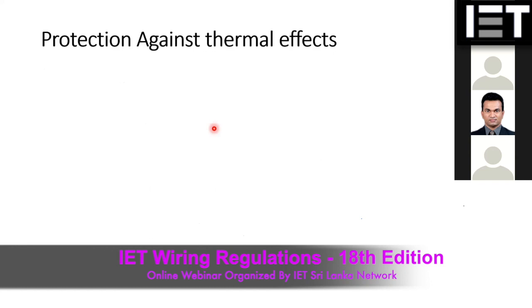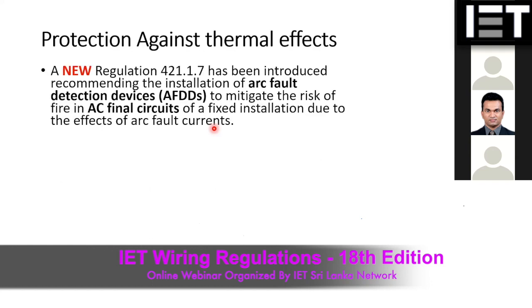And also there is a new addition for the protection against thermal effects. This is a completely new one, which the earlier version did not talk about. Now they are introducing a new protection requirement, fault detection, the arc fault detection. Arc faults are such that even when you switch on and off a switch, you can see a small arc inside the switch. So those are arcing. But if there is a sustained arc, that can create a fire hazard. Because of that, people realized that this is a major issue.